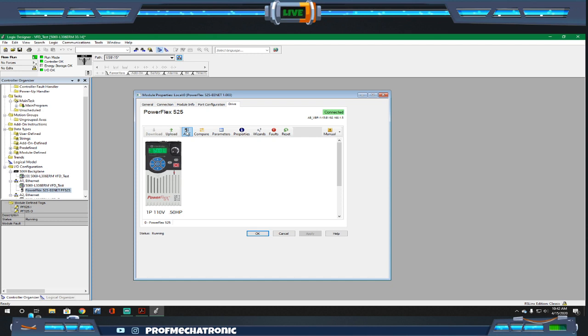So if a VFD were to break or blow up or become non-functional in any way, all you would have to do is basically set the IP address up on the new drive, plug your Ethernet cable back in, and plop that back into the system. From there, the PLC would dump all of the information that it had stored for that IP address and that drive and that compatibility back into the drive itself.